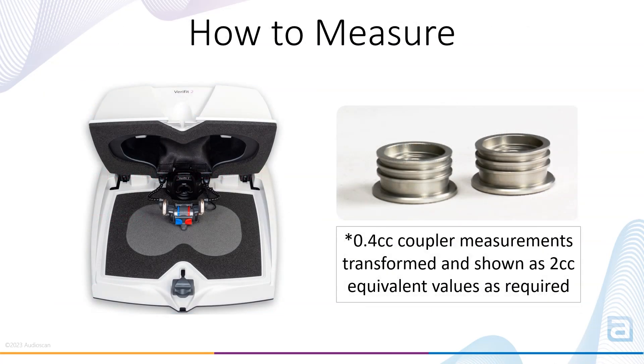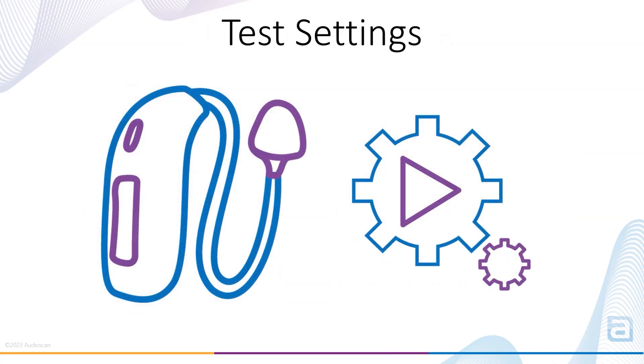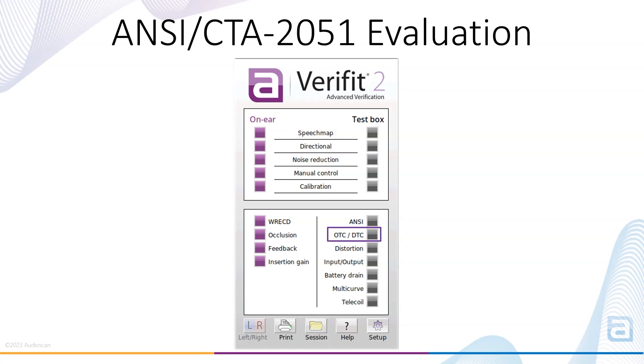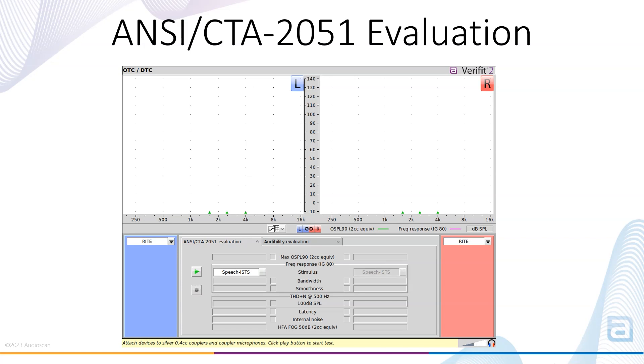Testing is performed in the binaural test box using 0.4 cc couplers, enabling efficient and accurate binaural testing of OTC and DTC devices. Measurements are automatically converted to 2 cc equivalent values as required by the test standard. Before running a test, if possible, set the OTC hearing aids to test mode or program the devices with full-on gain settings with the widest possible frequency range and non-linear adaptive processing minimized. To get started, select the OTC-DTC test suite from the Verifit 2 menu. With the ANSI/CTA-2051 evaluation tab selected, configure each device for left and right side, and configure the stimulus as speech or swept pure tones.